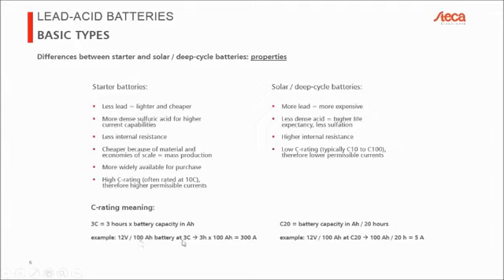We have a 100 amp hour battery rated at 3C. It means that the 3 is in front of the C, so it's a multiplication. 3 times 100 amp hours means we can extract 300 amps from this battery, so we can extract 3 times the capacity in current. This is definitely a high current battery. As soon as we have numbers in front of the C, we're typically talking about high current applications.